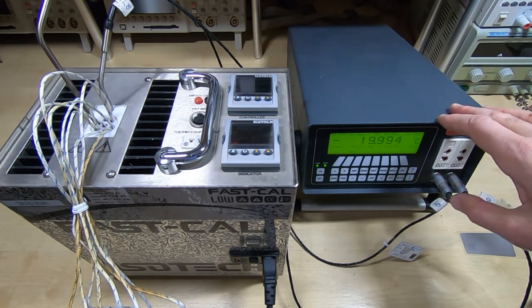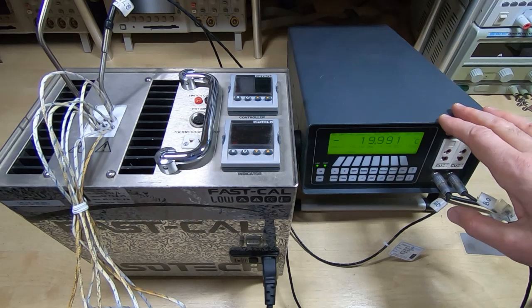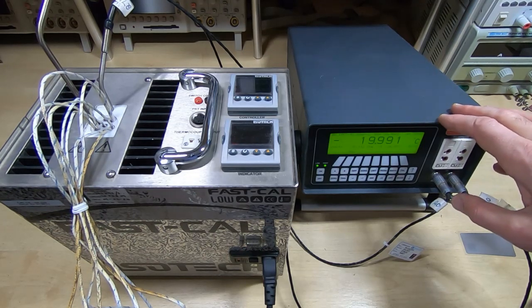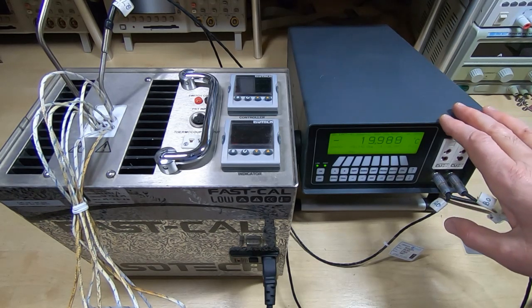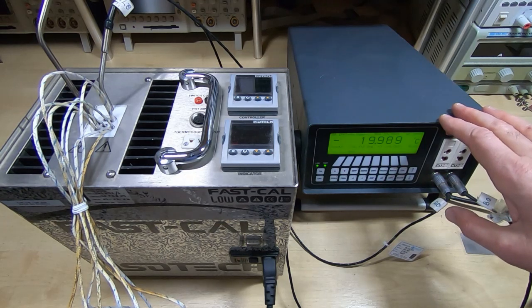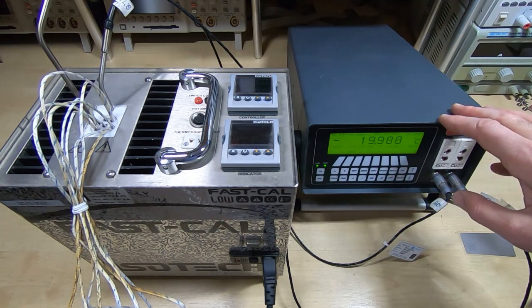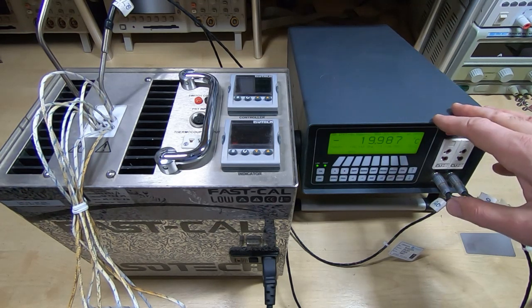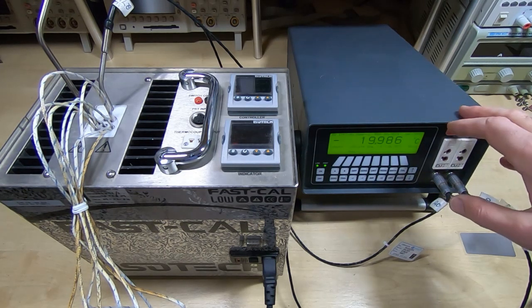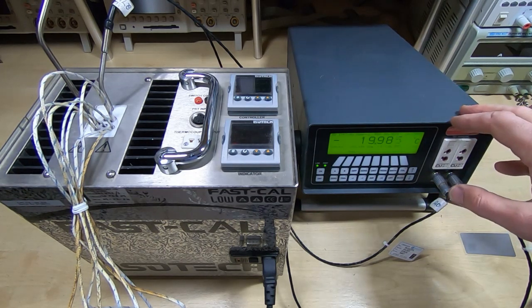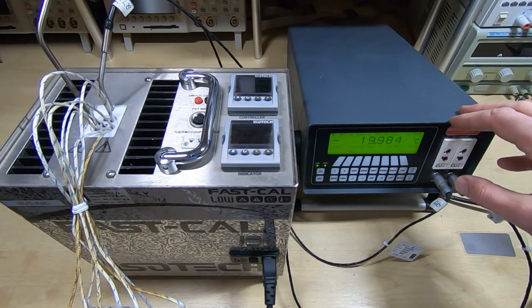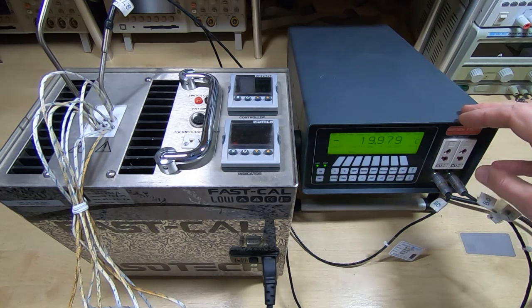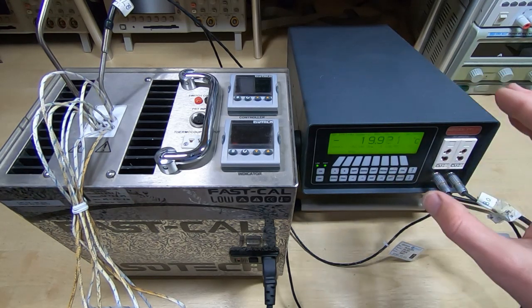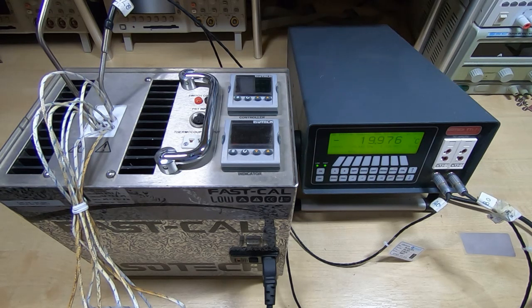The only reason I go so low when we're looking at a reflow oven that's going to be going up well over 200 degrees is because I want to look at the response of the machine, not just the peak temperature accuracy. And although it won't go down to below 0 or even close to 0, because I'm going well outside the range of the reflow oven, it gives me some confidence that the intermediate values are going to be accurate. So the next thing we do is we drive it up to the next temperature.